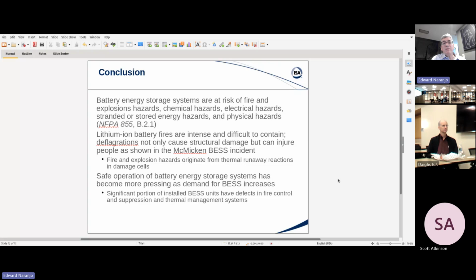Lithium-ion battery fires are very intense and very difficult to contain. Most fire emergency responders are not trained on these fires, so there's much to be done to protect firemen and also protect end users at the installation. I think the incident just illustrates the case quite well. The best method of protection is simply to use the appropriate standards—I believe those to be quite adequate. The main standard, as I pointed out, is 855, along with its satellite standards, NFPA 68 and NFPA 69.